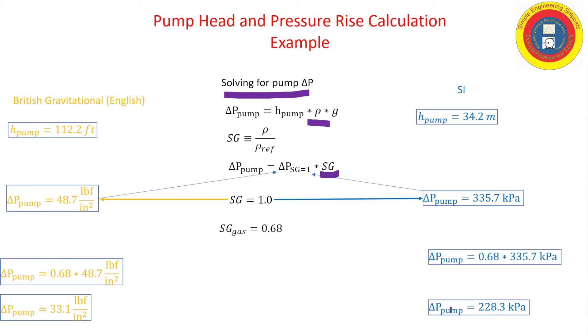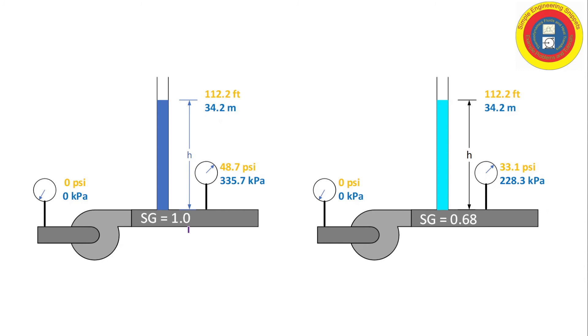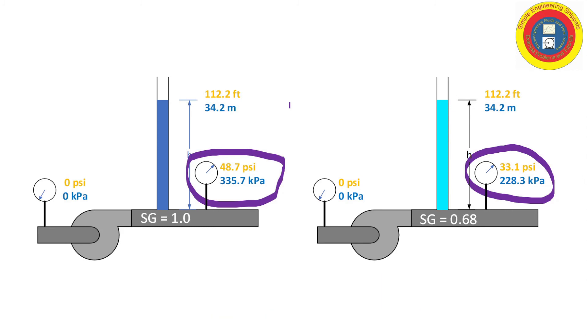So again, I want to reiterate that the head remains the same when we change specific gravity, but it is the discharge pressure or the pressure rise across the pump that is actually going to change. This is why pump manufacturers will specify their performance curves in terms of head. Typically, it's in head energy per weight; it could be energy per mass with dimensions of feet squared per second squared. Typically, it's energy per weight in units of feet or meters.